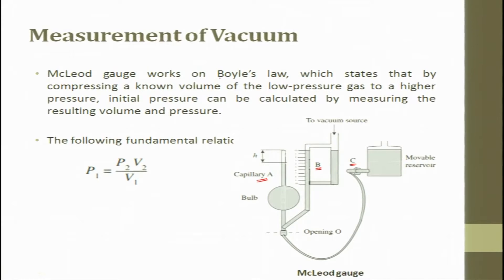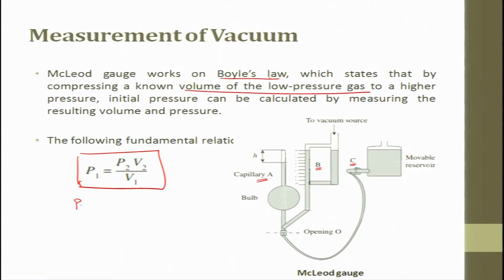The McLeod gauge works on Boyle's Law, which states that by compressing a known volume of low pressure gas to a higher pressure, the initial pressures can be calculated by measuring the resulting volume and pressure. The fundamental relationship is P1V1 = P2V2, rearranged as P1 = P2V2 / V1.